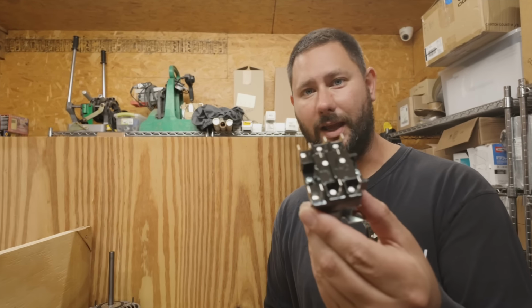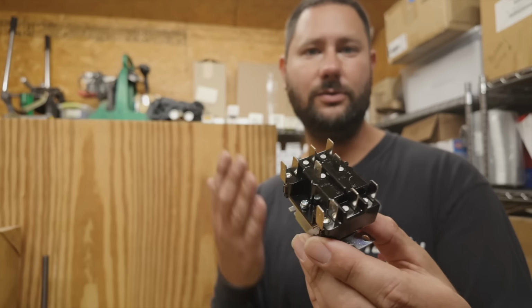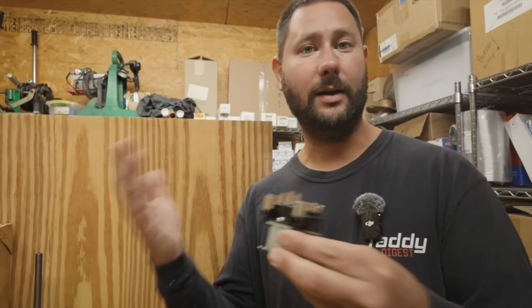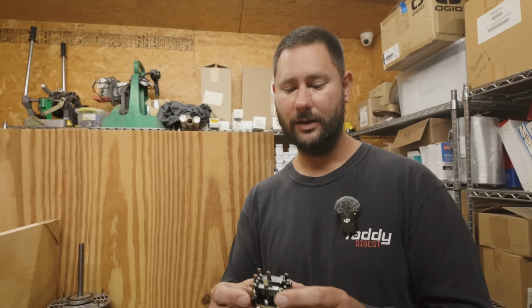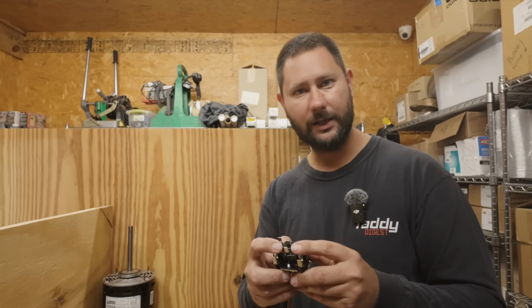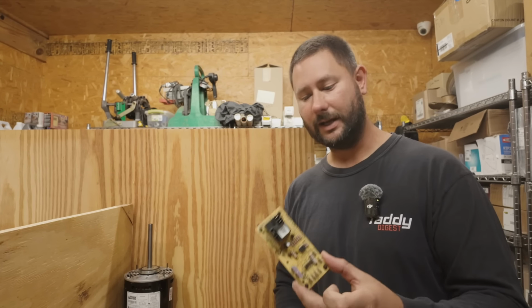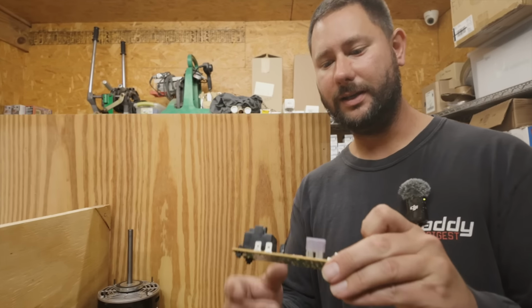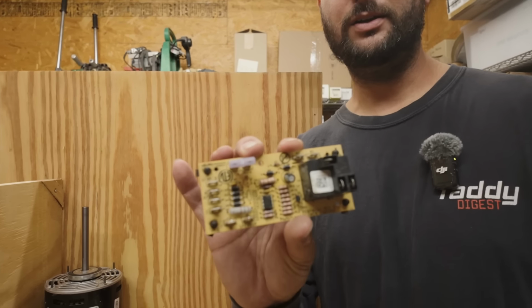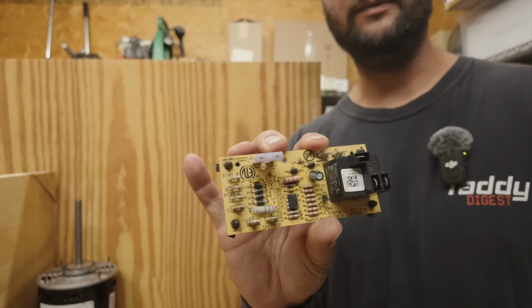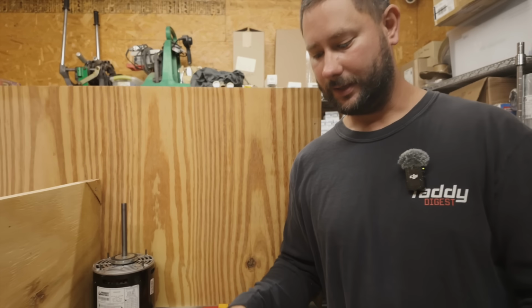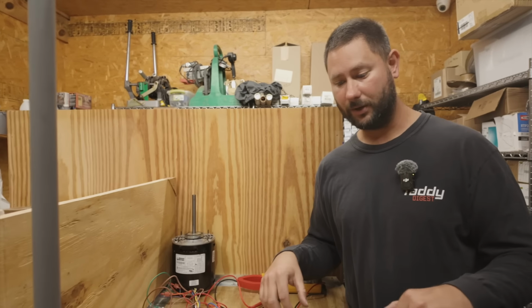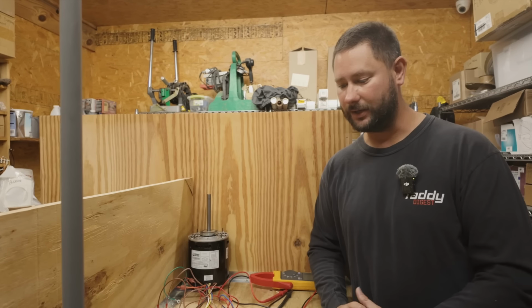We've got a switching relay, and typically you'll see this used to control a blower motor. So you've got a coil, and normally closed and normally open contacts, which we're going to go over. Then I've got a little board here, and this board is a blower control board. Usually these are time delay boards, so they've got a little time delay. We've gone over most of the components we're going to be using. Now let's go over the setup.